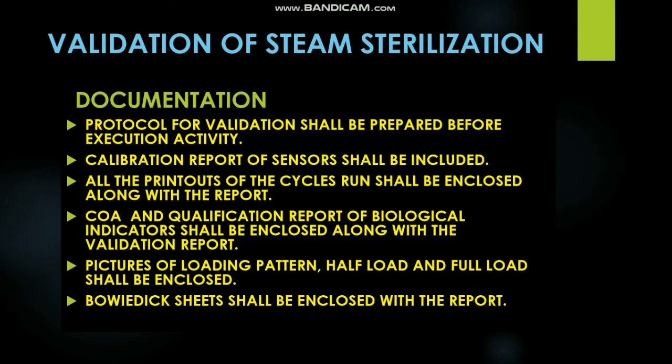Now after doing validation activities, we need to come to the documentation part. After qualification of the steam sterilizer, now comes documentation. In documentation, we need to prepare the protocol for the validation of the steam sterilizer, specifying what needs to be done. The half load pattern must be specified: what the half load pattern will be, the operation time, the set temperatures, and the loading patterns.